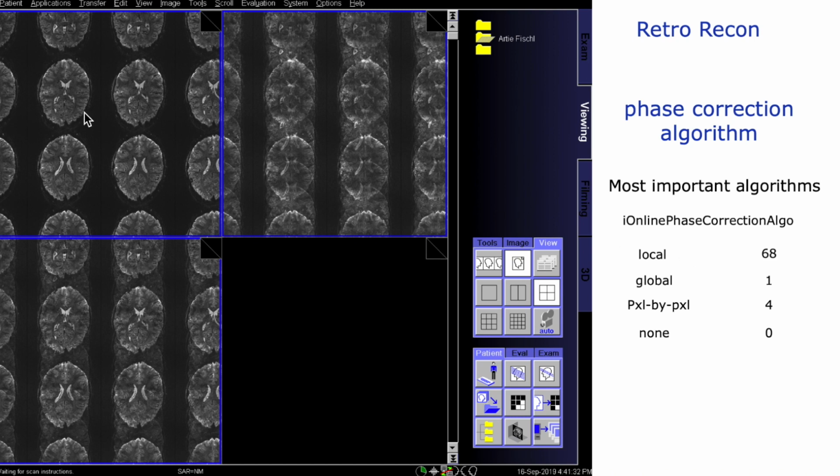And here I want to show you a few examples of reconstructing the same data set with these different phase correction methods from our participant RT. And you can see that the 68 for me kind of looks the cleanest. And the global one down here is also kind of okay, but you have increased ghosts, because here I acquired a data set being very, very close to these acoustic resonances. And the global phase correction scheme cannot really fully account for that, because we have a lot of ramp sampling, and there a certain delay in k-space refers to a different phase offset that needs to be corrected.